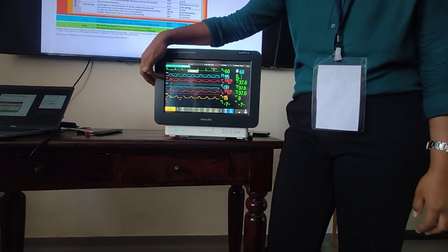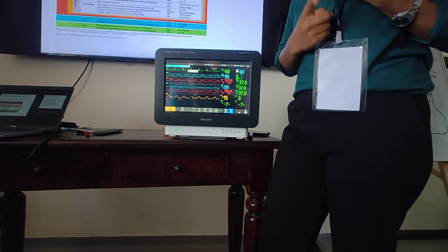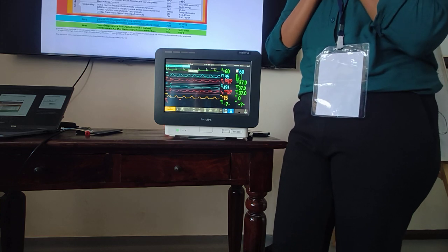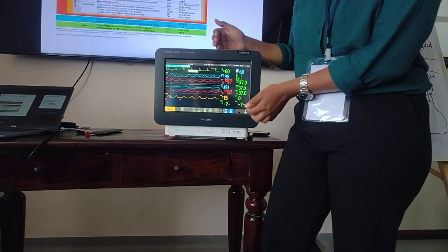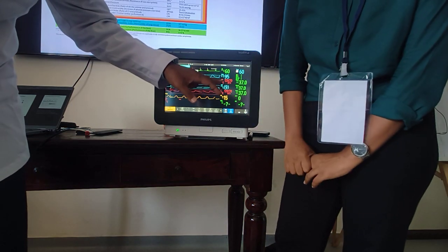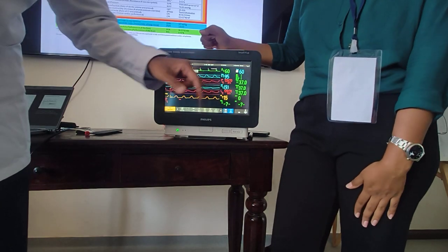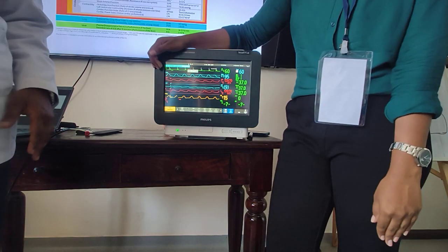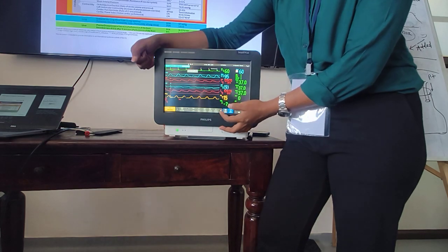Second thing, as I told you, is zeroing the ABP and CVP, your arterial line and CVP line. If I put ART, will it work? It will work, you just need to change the label. Here it is written ABP. The label has to be the same, whether you use ART or ABP. The monitor should know from which instance it has to pick a signal.